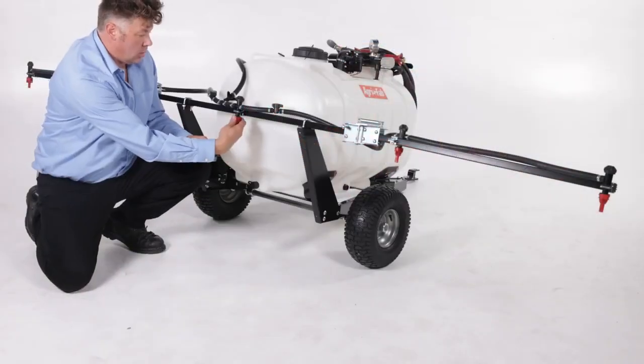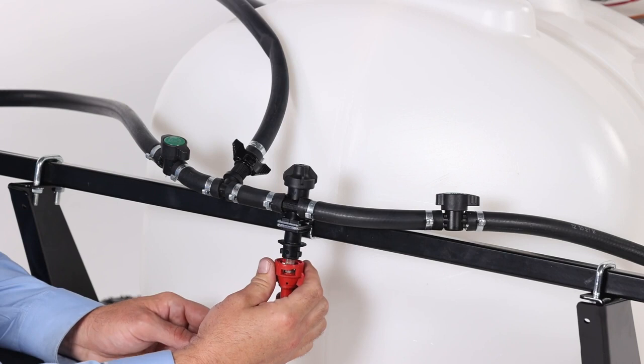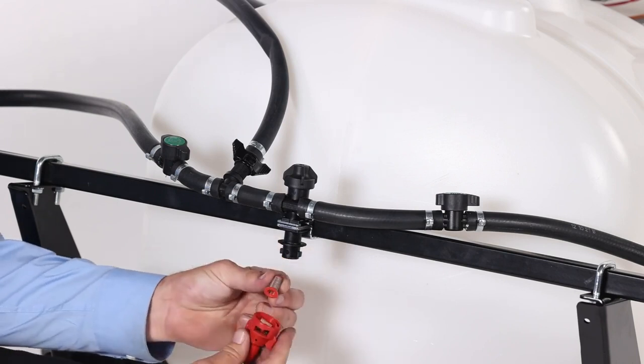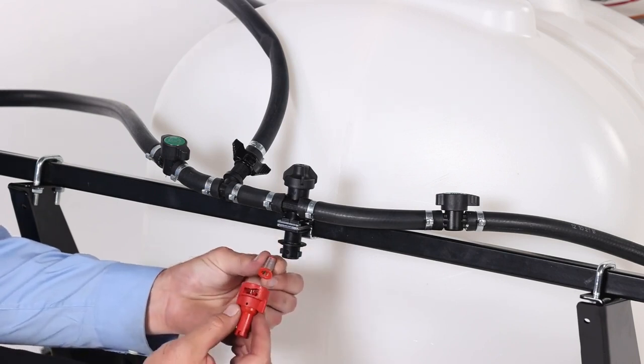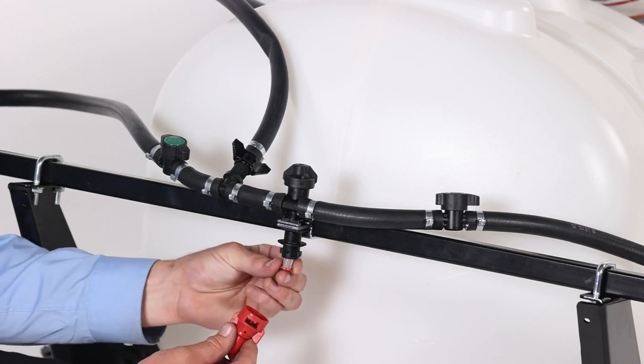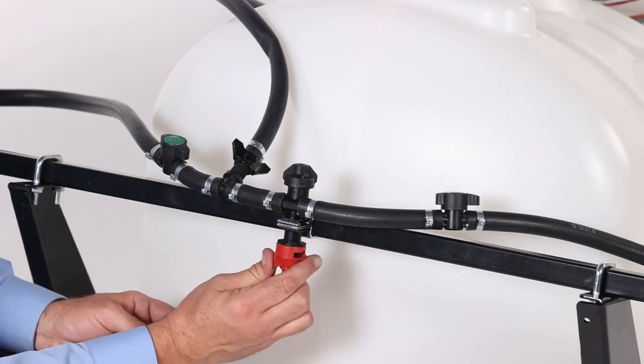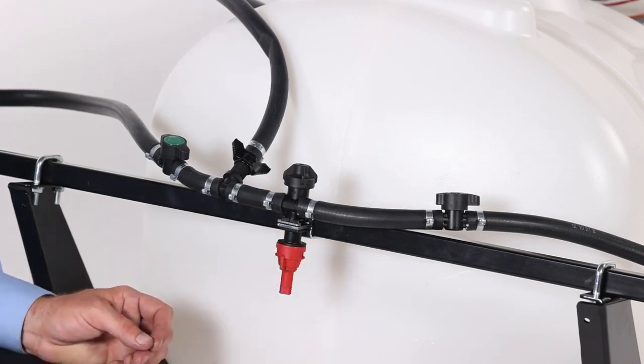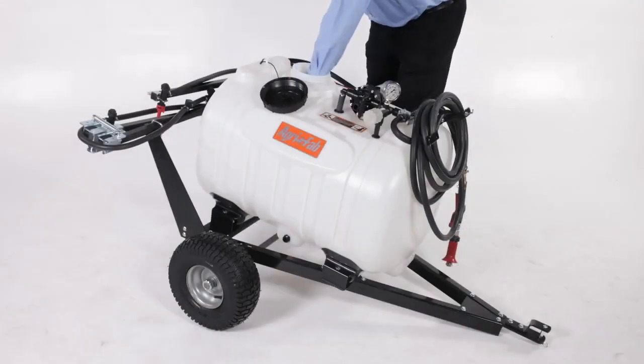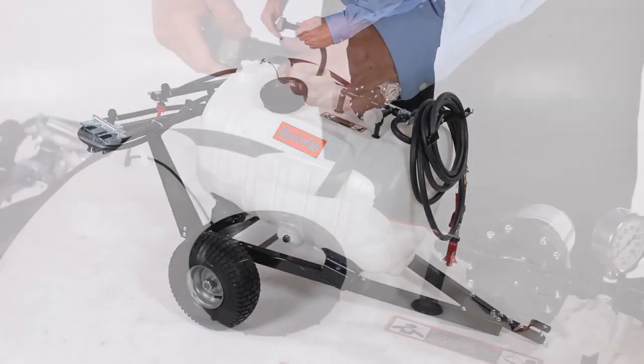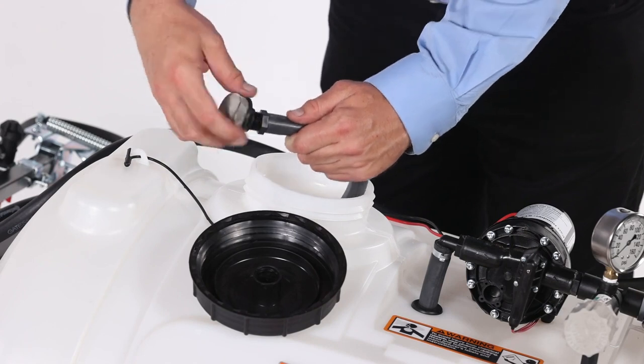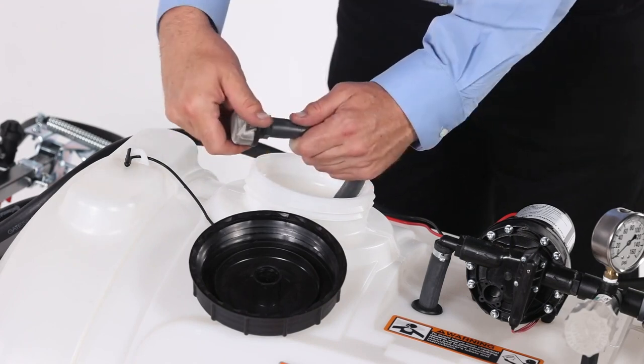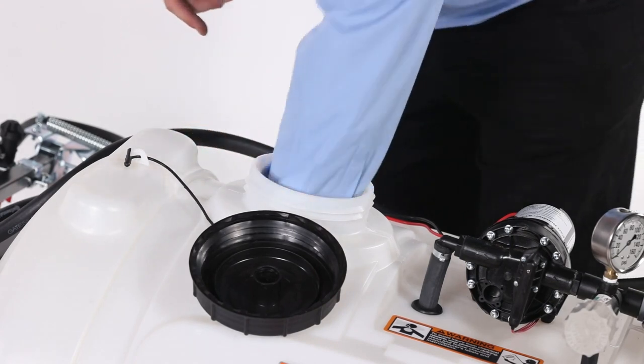To clean spray tips, remove the spray nozzle and screen. Wash the screen and spray tip in a non-flammable solvent. Now insert the screen and secure the spray nozzle. To clean the pump suction screen, remove the tank cover. Then unscrew the suction screen and clean it with liquid detergent and warm water. When reinstalling it, ensure it reaches the lowest depression in the tank.